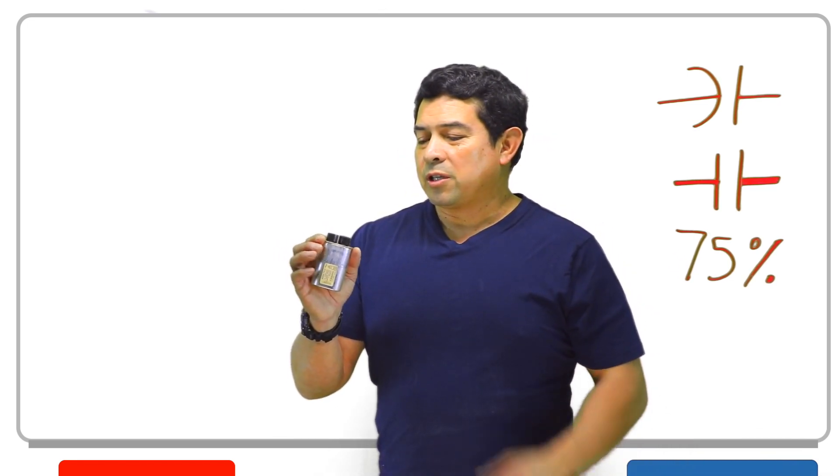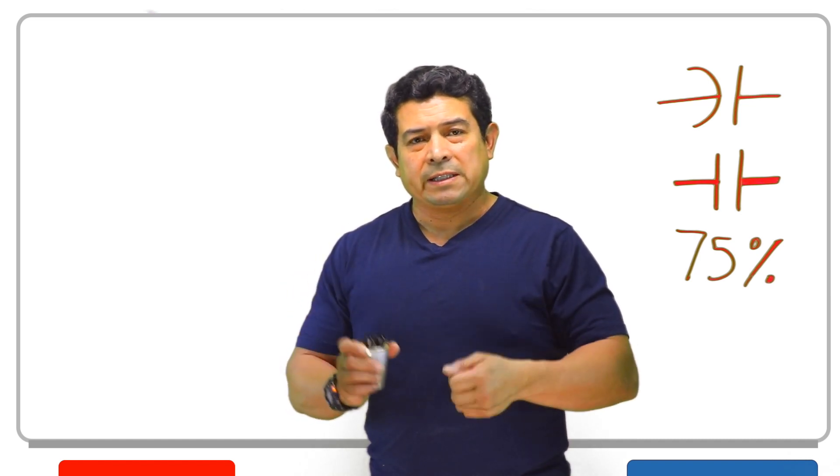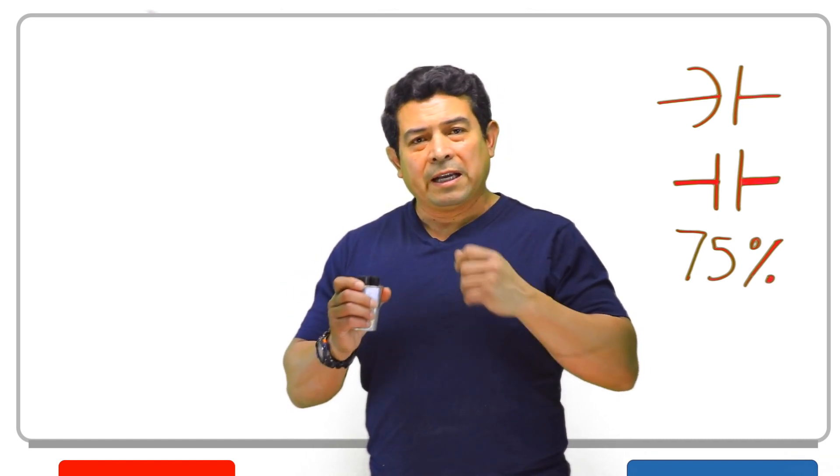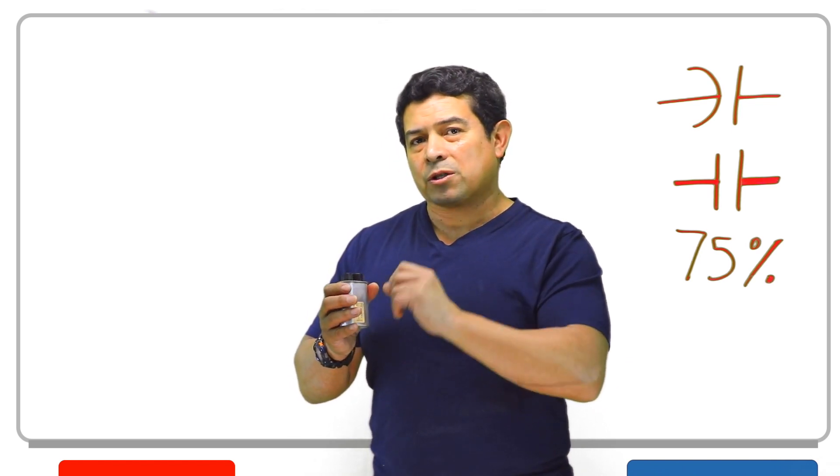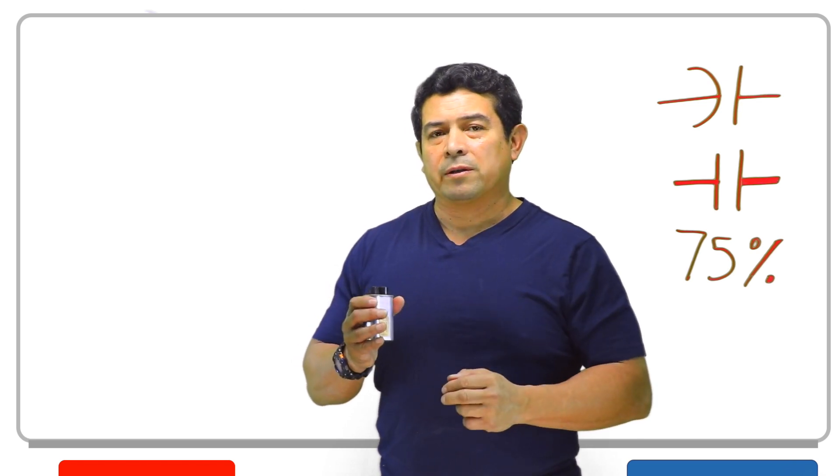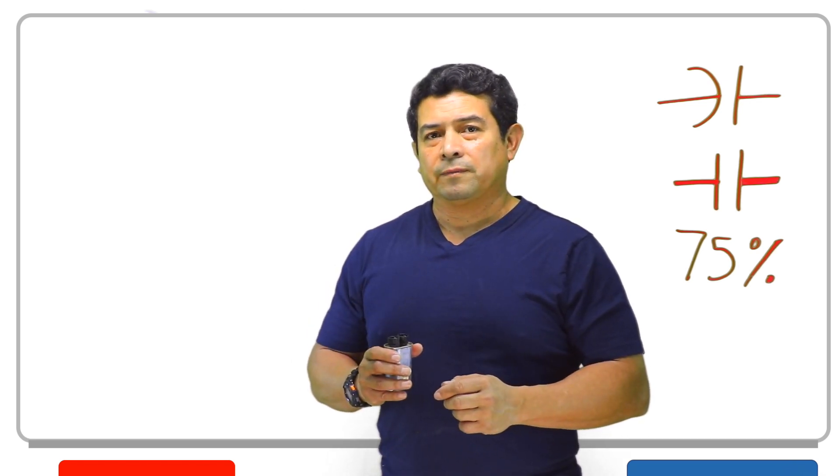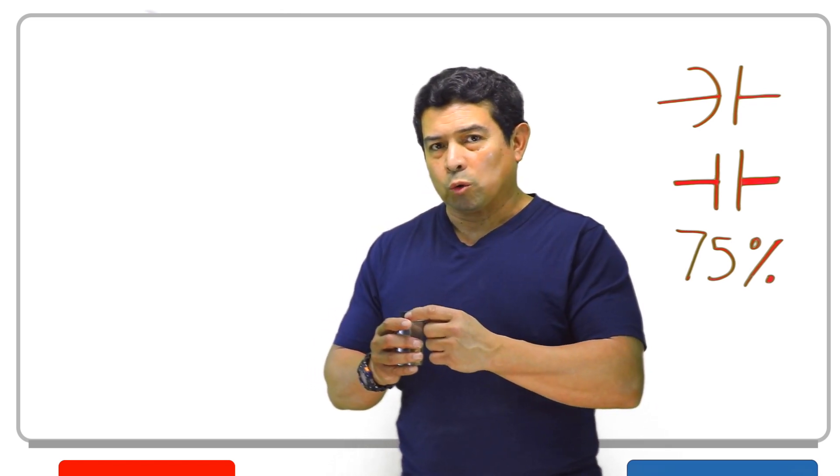So these capacitors, yes, you can have the run capacitor. You have the start capacitor. To test them, you test them with a microfarad tester. It has to actually give you the number. I have seen some that just light up. Well, you need to know exactly how many microfarads this can charge to. Again, like I said, be careful with these because these will hold a charge.